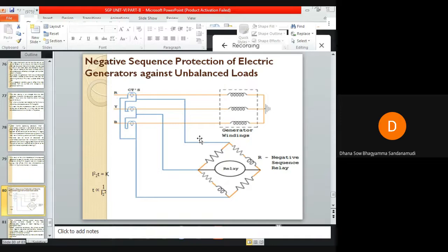Rotor overheating can also be due to unbalanced external faults which are not cleared quickly. Open circuiting of a phase, or failure of one phase's contacts of the circuit breaker, can also lead to overheating of the rotor. Now, to save the rotor from getting heated up under such conditions, we need a negative sequence relay. I hope you remember we have already discussed the negative sequence relay. This negative sequence relay will sense this and it will operate.